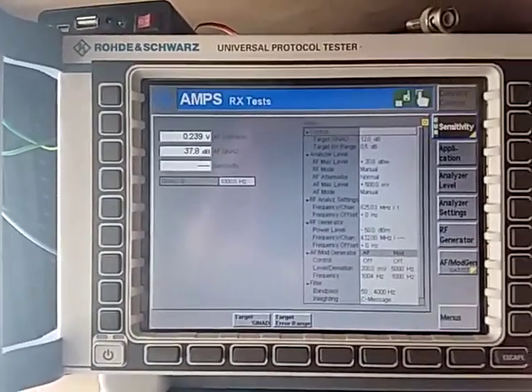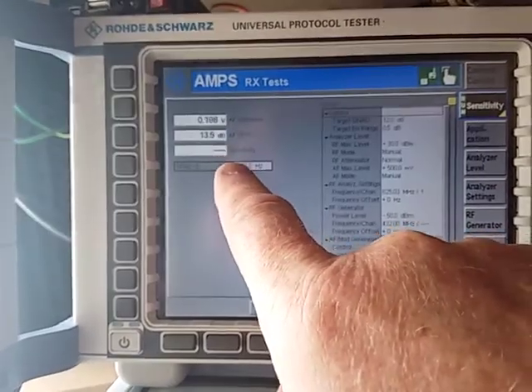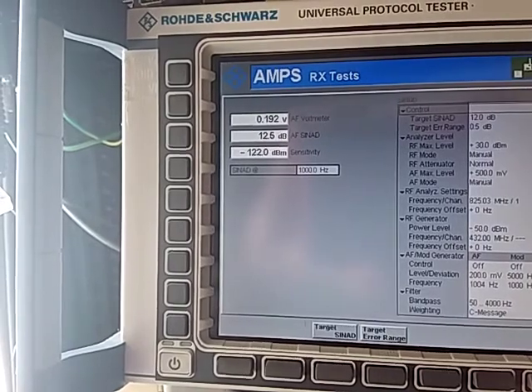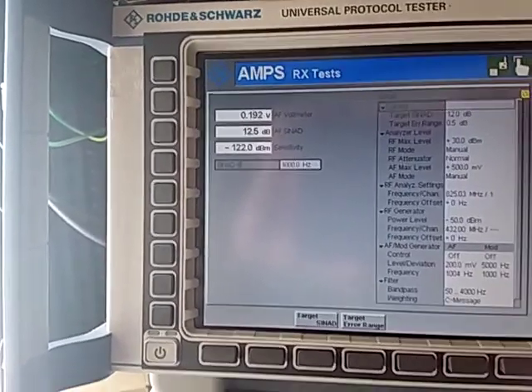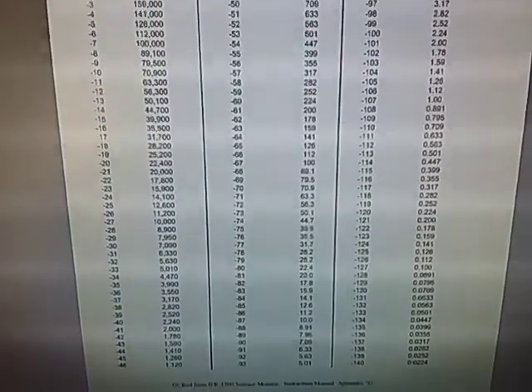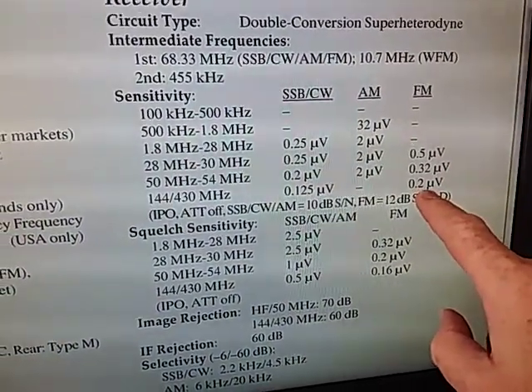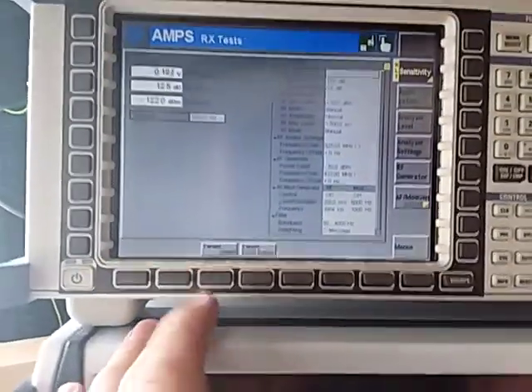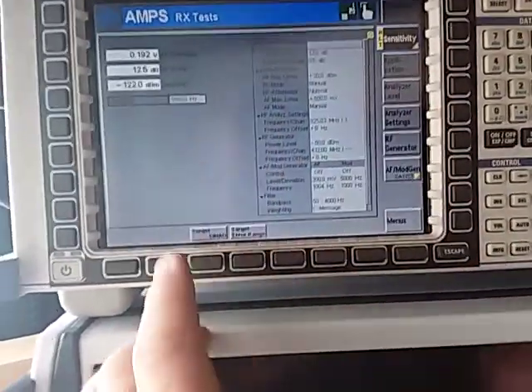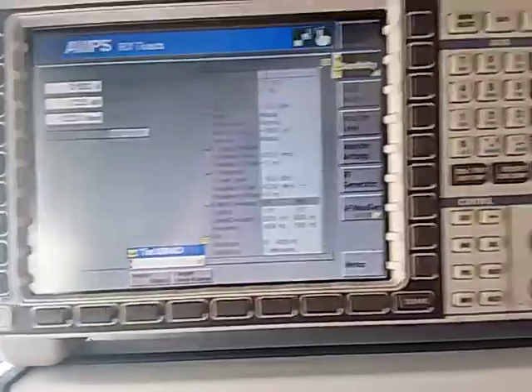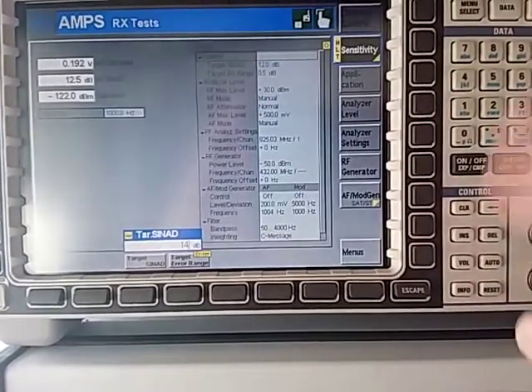That's all we need to do. The analyzer is outputting different RF levels and it will tell us what RF level it took to get to 12 dB SINAD. It's finished its testing and it's saying the sensitivity is minus 122 dBm. If we go to our tables and look at 122, we can see that is 0.178 microvolts, which is less than — that is, better than — our quoted 0.2 microvolts. You may wonder why this stopped at 12 dB SINAD. On this screen you can tell it where to stop. By default it is set to 12 dB, which is an industry standard.